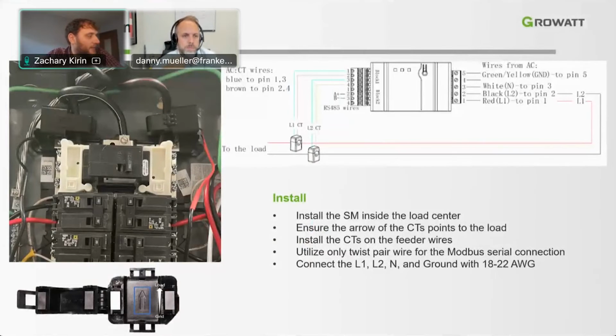You can install this smart meter into the load center of your home with the CTs. Make sure that the CTs are pointing in the proper direction, where the arrow points to the load side. The CTs will be installed at the feeder wires on the customer load center, so directly on these feeder wires up top, and the actual device will be mounted on a DIN rail. The most important thing to note about the smart meter is if you mix up the polarity of the CT, or the CT is facing in the wrong direction, you will not be receiving proper data readings. So it's very important to make sure the arrow is pointed directly at the load center. The arrow would be pointing down in this case.